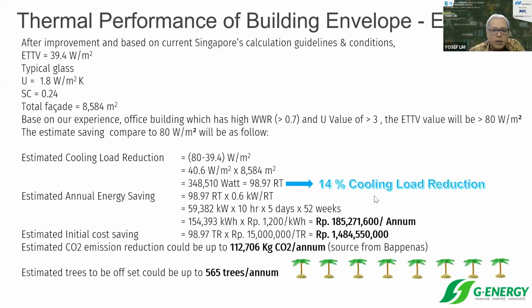I'll calculate based on this 98 tons multiplied by the chiller system efficiency, let's say 0.6 kilowatts per ton, which is what we designed for in this project. In reality, they achieved 0.57 kilowatts per ton, which is even better. Multiply this efficiency by 10 hours a day, since this is an office building operating 5 days a week, then by 52 weeks a year, and we get a result of 154,000 kilowatt hours per annum.